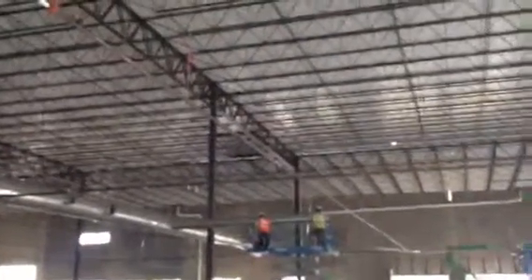If that's the case, they'll continue running the low pressure side of the fan power boxes — minus canvases, which we do not have yet. There's our main. I got my drops ordered to fill in the gaps there. That gap is because of this piece of damaged 28-inch that was crushed by a boom basket set down on it. There's the rest of our main trunk. Same thing with RTU1 — calculate the drops, get those called in and get them in production.